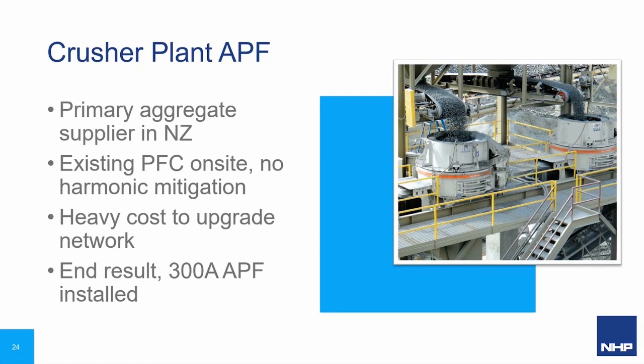So we were first approached by the quarry to look at improving the very poor power factor on the generator-fed portion of the plant. At the time, there was a lot of concern around the use of power factor correction in the context of the generators, fear about going into leading power factor and so on. However, a very carefully engineered 400 kVAR capacitor-based PFC system was installed and commissioned by NHP, and this immediately reduced their apparent power draw to the point where they could completely switch off one of the generators, with associated costs of fuel and maintenance. So, yeah.